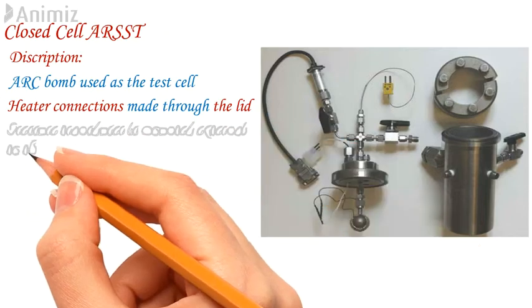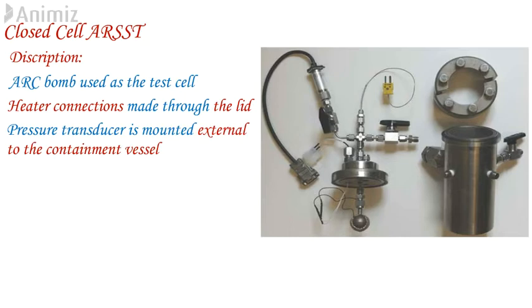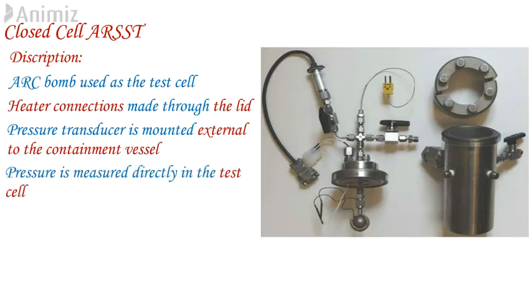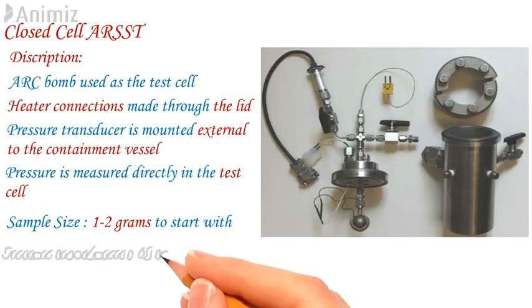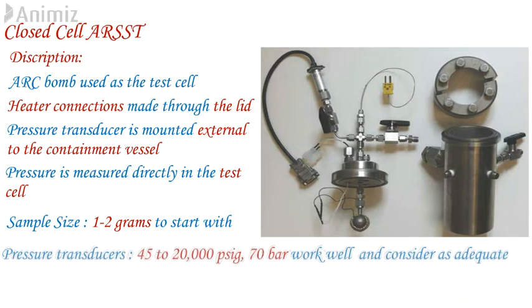The pressure transducer is mounted external to the containment vessel, while the sample thermocouple passes down inside the pressure tube. Good agitation is achieved using a small magnetic stirrer bar. In the closed cell configuration, pressure is measured directly in the test cell. Since the available void space is much less than for an open cell vent sizing test, it is recommended that the test cell fill fraction be substantially less than in vent sizing tests — particularly for gas generation systems. It is suggested to start with no more than one to two grams of sample. ARSST pressure transducers range from 45 to 20,000 PSIG full scale; for most applications, a standard 1000 PSIG (70 bar) transducer works well, though a lower range model may be preferred for better pressure resolution.